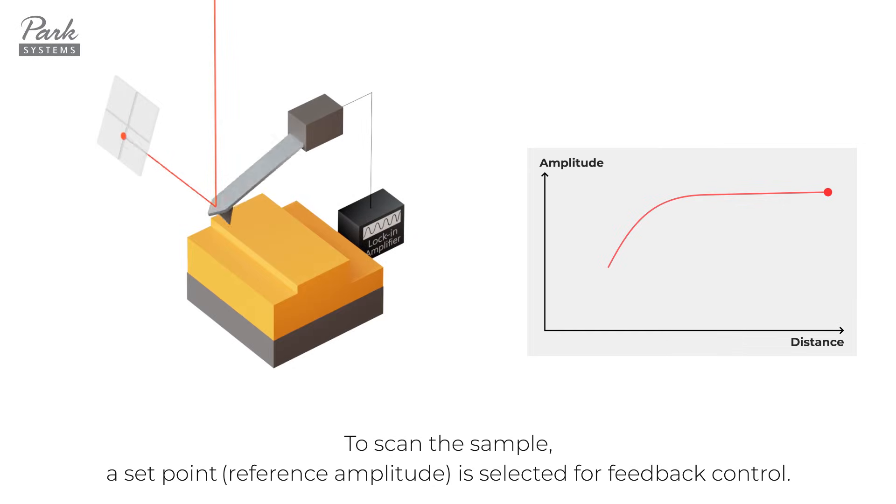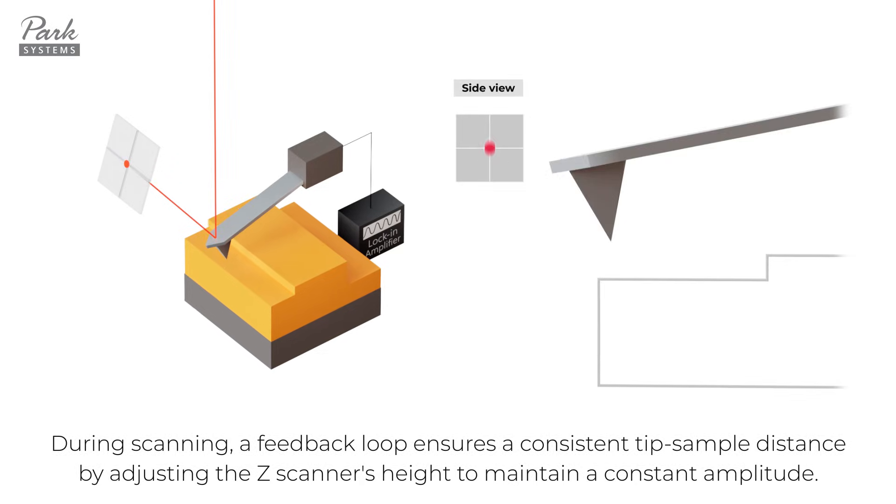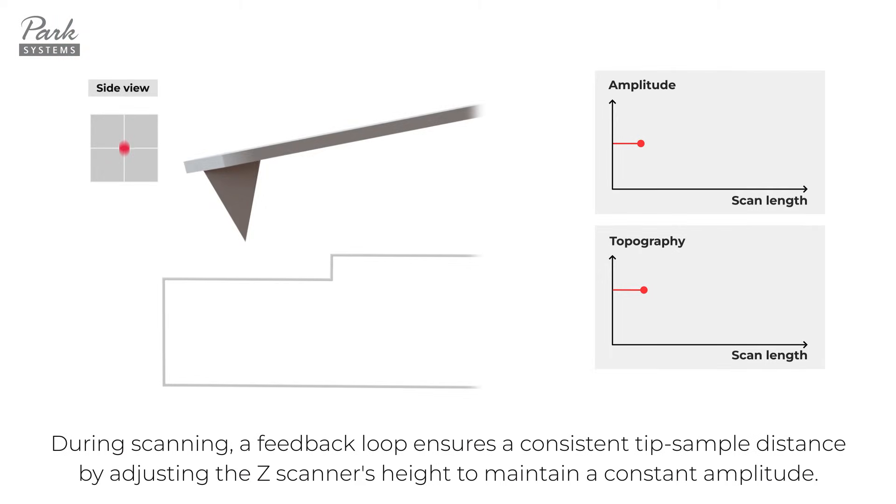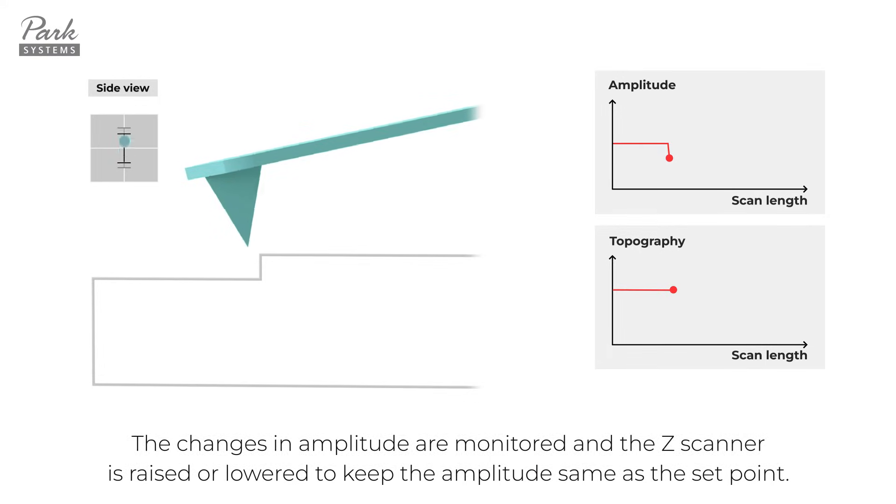To scan the sample, a set point is selected for feedback control. During scanning, a feedback loop ensures a consistent tip-sample distance by adjusting the Z-scanner's height to maintain a constant amplitude. The changes in amplitude are monitored and the Z-scanner is raised or lowered to keep the amplitude same as the set point.